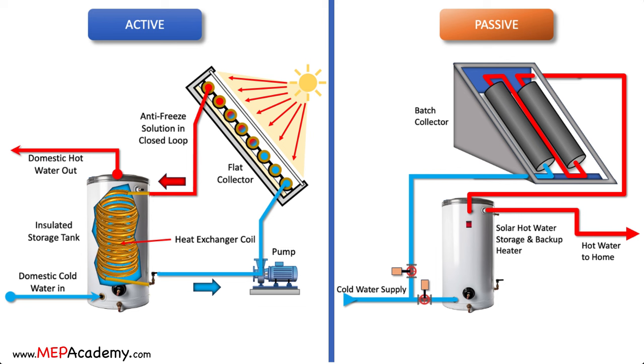Most solar water heaters require a properly insulated storage tank. These tanks typically feature an extra outlet and inlet that are linked to the collector. In two-tank configurations, the solar water heater heats the water in advance of it entering the standard water heater. Conversely, in one-tank setups, the backup heater is integrated with the solar storage within a single tank.